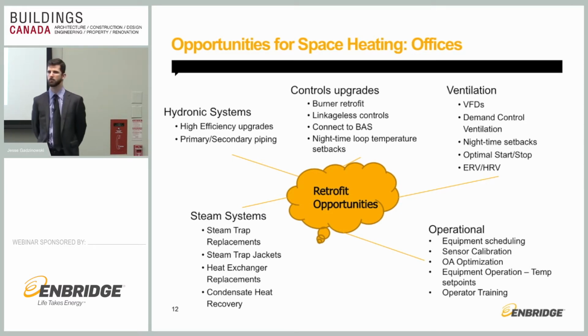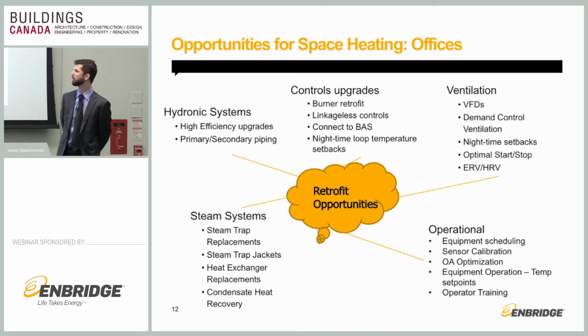So some heat exchanger retrofits are happening this year where you can have more of a flooded unit where you're subcooling, you're using some of the BTUs in that 212 degree Fahrenheit condensate. Maybe you can bring that down to around 180 F before you have to quench it. So the delta between that 212 and 180, you can capture that and put it into your domestic hot water, or you can preheat the incoming water for whatever you would need it for, really.